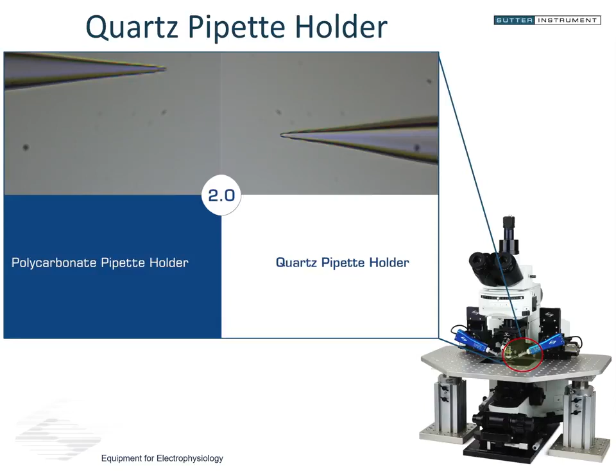Well, we set up a little test procedure to put a heating filament underneath the head stage of the pipette. And we did this test with both pipette holder types placed above the heating filament. And what we found is that the polycarbonate pipette holder, very quickly, almost immediately, this is a 2-second heating cycle of the filament that's placed under there, is displaced extremely. We see it move almost out of the field of view of the microscope area here. Whereas the quartz pipette holder is virtually completely stable.